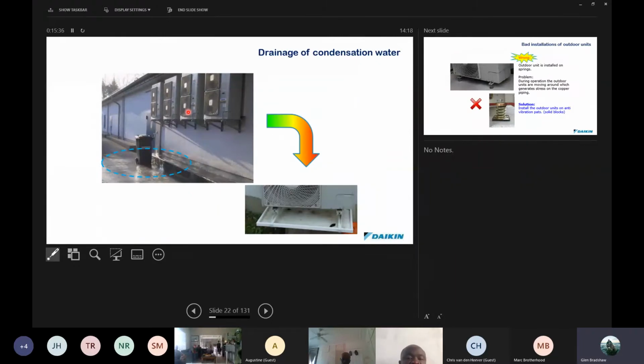Another consideration for placing of condensers is remember that in the cooler months when they're in heating, water will be flowing out of these condensers, and you must make provision to remove that water away from the building. Otherwise, it's going to become a safety and health issue. Safety because people can slip in it. Health because over time, algae and things like that grow in the water. And also, it devalues the structure of the building. Okay. All right, so drip trays underneath the unit is a good way of going.